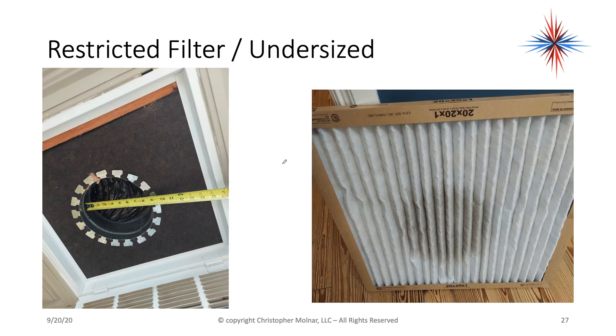Restricted filters and undersized filter grills are also a problem. Looking at this filter without even pulling it out, you can see the dirt pattern where the boot is. This is only an 8-inch round on a 3-ton system — no way is it going to have enough airflow. And if you look up in there, this flex duct is coming off and going directly to the left — they're trying to make a 90-degree elbow just using flex duct. It's going to collapse. The solution is a bigger boot and using a 90-degree metal elbow before going to flex.